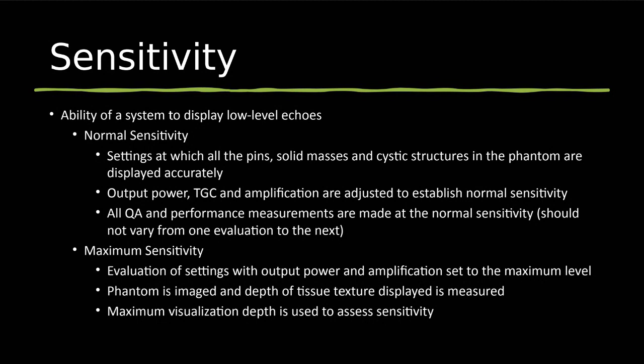and we're testing that sensitivity of how much can our system pick up with these standard average values versus maximum sensitivity, where we're putting that output power all the way to its maximum to see what that lowest amount of information we can actually get from that picture is and how useful is that information. Again, we're not doing this on a real patient. We're doing this on a phantom because we know we don't want to be using our maximum output power for bioeffect reasons, but it's saying to the physicist, this machine can evaluate this low amount of echoes with the settings being set all the way to the maximum.